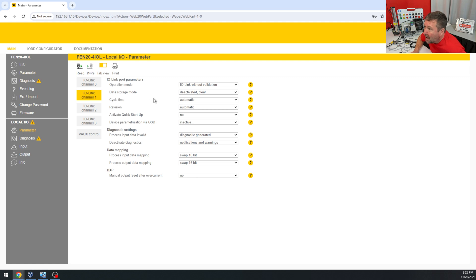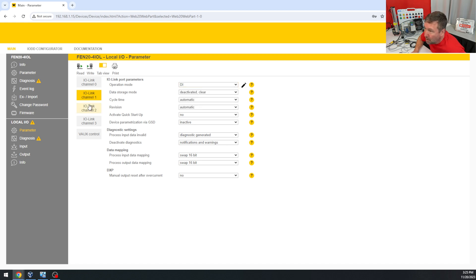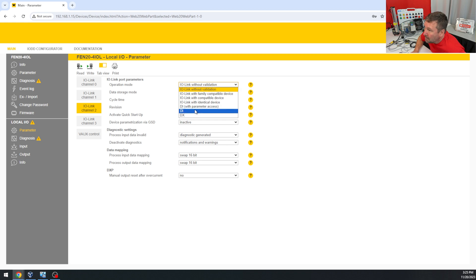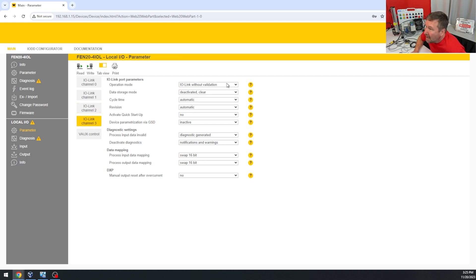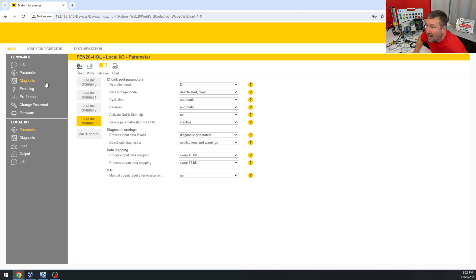So then I went back to the main and went to parameters, and once logged in I could change these. So right here I just want a regular digital input for channel one, a regular digital input for channel two, and a regular digital input for channel three. I'm going to write that and notice that my triangles went away.